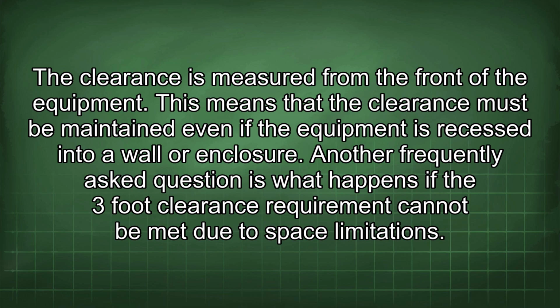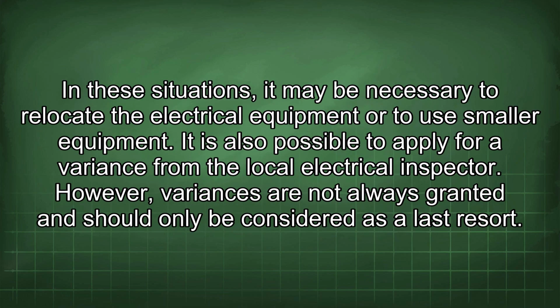Another frequently asked question is what happens if the 3-foot clearance requirement cannot be met due to space limitations. In these situations, it may be necessary to relocate the electrical equipment or to use smaller equipment. It is also possible to apply for a variance from the local electrical inspector. However, variances are not always granted and should only be considered as a last resort.